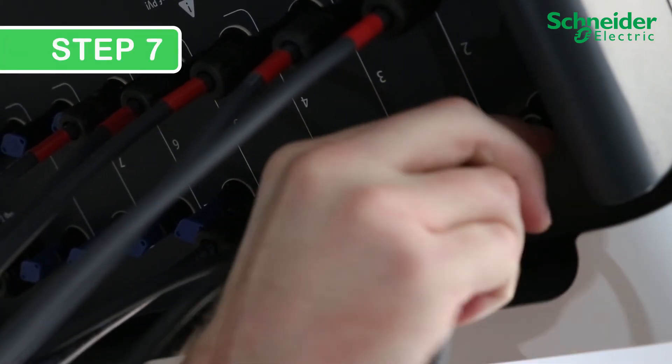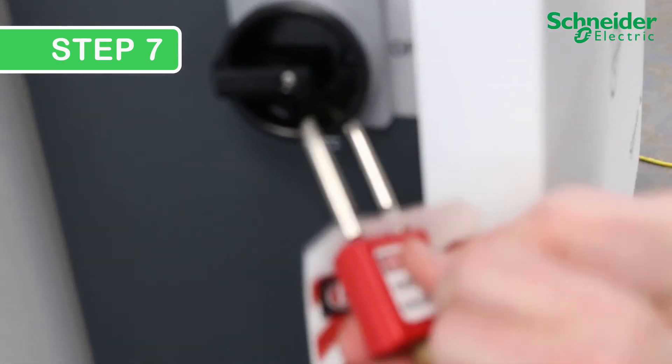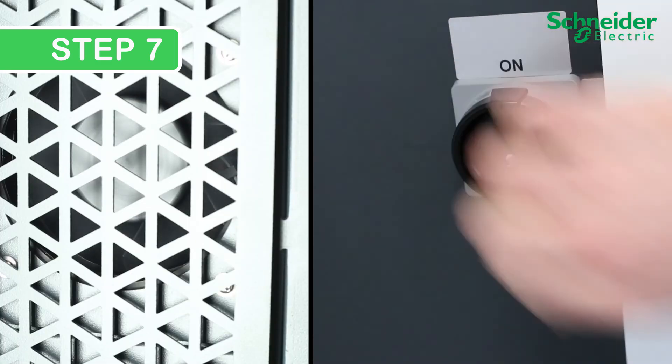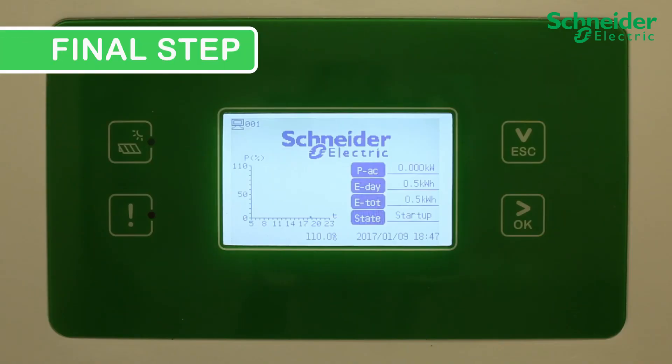Step 7. Replace the front cover by tightening the six T30 screws to 4.3 Nm or 3.2 lb-foot. Reinstall the PV string cables onto the input connectors and restore DC and AC power to the CL60 following lockout tagout, site, and jurisdictional safety procedures. Final step: ensure the DC SPD alarm is clear and the CL60 is producing power.